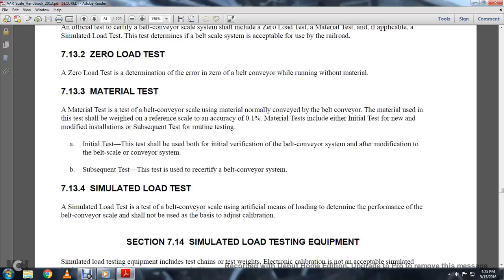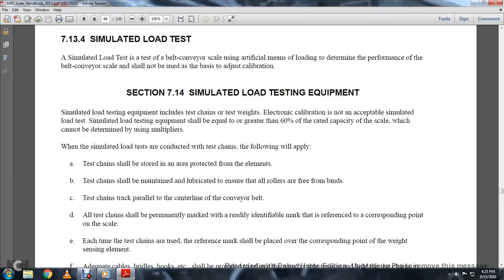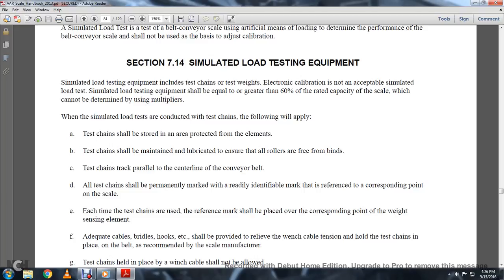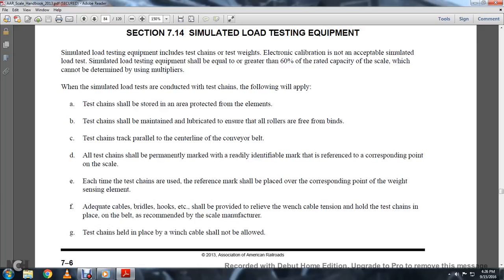Section 713, Simulated Load Test. The simulated load test is a belt conveyor scale test using artificial means of loading to determine the performance of the belt conveyor scale; it should not be used as the basis for adjusting calibration. Section 714, Simulated Load Testing Equipment. Electronic calibration is not acceptable. Simulated load testing equipment shall load greater than 60% of the rated capacity of the scale. When simulated load testing is conducted with test chains, the chains should be stored in a protected area, maintained and lubricated to ensure all rollers are free of binding.